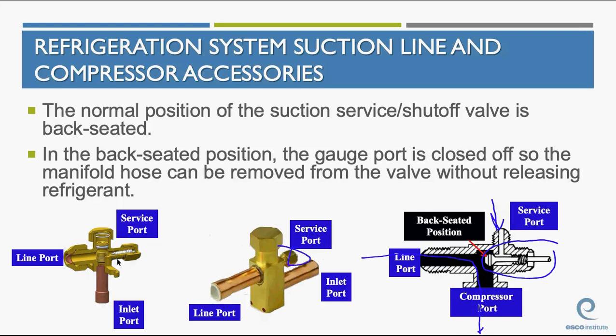Okay, again, here, service port. Okay, here, service port. Notice the caps on these service ports. You always want to have things capped. Okay, but based on where the valve position is, I'm either blocking off the line port, the service port, or I have everything open. Three-way valves. In the back-seated position, the gauge port is closed off so the manifold can be removed from the valve without releasing refrigerant. Any question on three-way valves? There's going to probably be about 2 or 3 questions throughout the test on three-way valves. Back-seated is normal operating position.